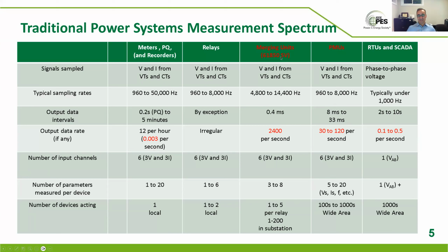We have IEC 61850 sampled value merging units with the standard 61869, with recommended sampling rates of 4.8 kilohertz or 14.4 kilohertz. 4.8 is for basic metering and protection applications. 14.4 is mostly for power quality applications. And the communication rate for both of them is about 2400 hertz, meaning you pack 2 measurements or 6 measurements in each packet that you send. That's a recommended value. 3 voltages, 3 currents, or you could say 4 voltages and 4 currents if you also send neutrals. And usually those are sent or subscribed by up to 4 or 5 relays in the substation. So there are not too many endpoints to get data from one merging unit, basically.